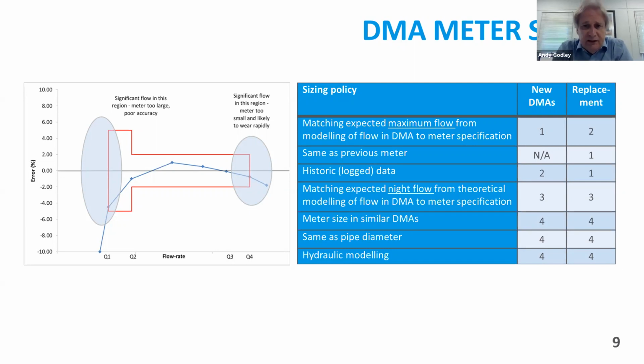On the right hand side, that little table is from a survey we did for a number of water companies, looking at how they specified a meter for a particular DMA, what size they would choose. The most common approach is modelling the flows, looking at the properties you've got in that DMA, and working out the ideal size of meter. So not just putting in a meter that's exactly the same as the pipe diameter, because many pipes are oversized to cope with future expansion in the area, new housing developments, or because what was originally in the area may have been commercial or industrial properties that have downsized or adopted more water efficient processes, and therefore the pipe is still too big.